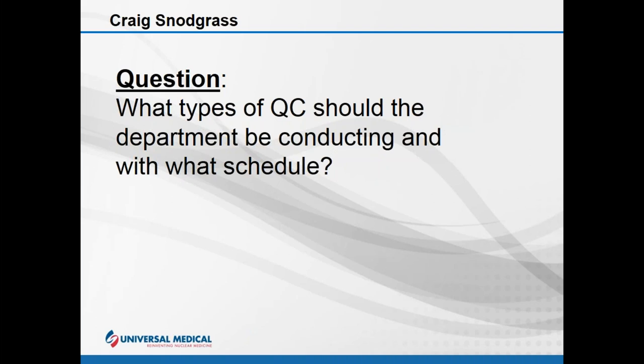So if you're completing an extrinsic cobalt, you'd want the cobalt to peak around 122 to 123 keV. And with technetium, you want to be in the 140 keV range.